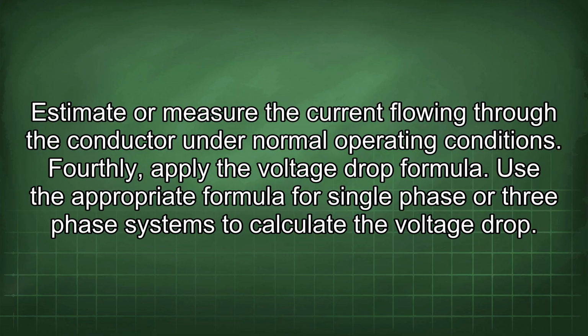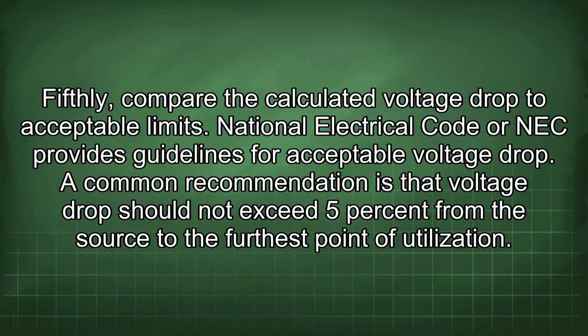Fourthly, apply the voltage drop formula. Use the appropriate formula for single-phase or three-phase systems to calculate the voltage drop. Fifthly, compare the calculated voltage drop to acceptable limits. National Electrical Code or NEC provides guidelines for acceptable voltage drop. A common recommendation is that voltage drop should not exceed 5% from the source to the furthest point of utilization.